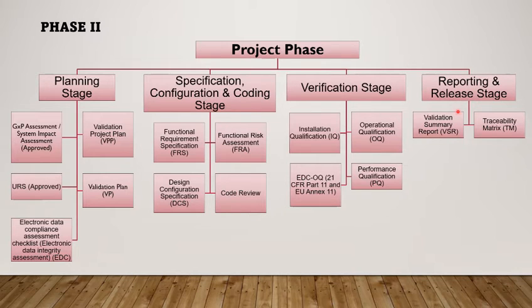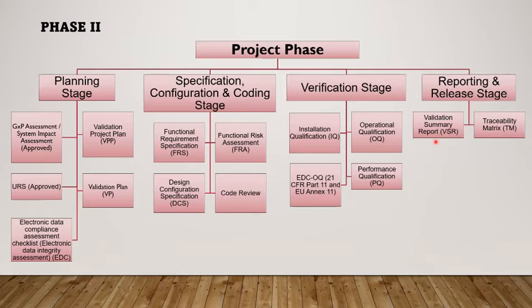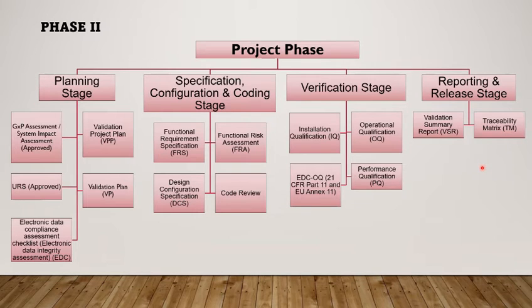The fourth stage is reporting and release. All activities performed during the project phase shall be summarized in this stage. The validation summary report states the validation overview and IQ/OQ/PQ testing summary, details of all activities performed, any deviations observed and CAPA taken, risk assessment against deviations observed, and also includes a statement of fitness for intended use. Once the validation summary report is prepared and approved, the system can be released for routine activity. Prior to release, ensure availability of the system inventory index, system owner, end user training, users log, system operating procedure, and maintenance and calibration procedures. A traceability matrix shall also be prepared to ensure that all applicable requirements mentioned in the URS and FRS have been verified.